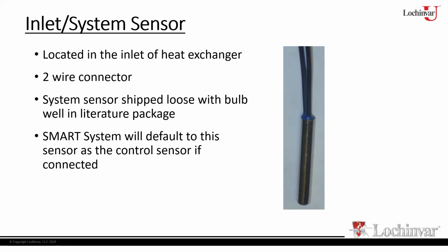If it's a water heater, you've got to use a tank sensor or a tank thermostat for the system to work correctly. I'd always recommend the sensor inside the storage tank. If it's a hydronic heating boiler, I would prefer to see what's going on in the system loop. So again, I would recommend using the system sensor.